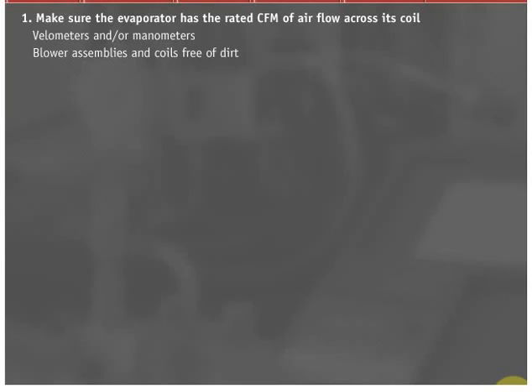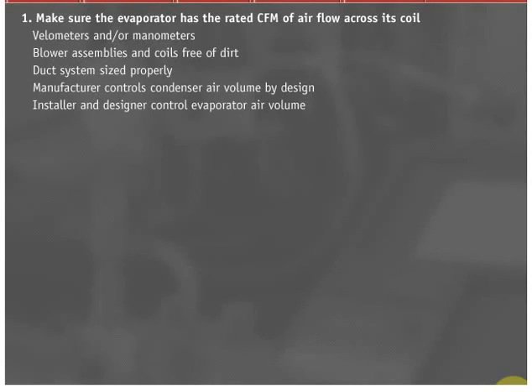Step 1: Make sure the evaporator has the rated CFM of airflow across its coil. Velometers and/or manometers with proper equations will assist in calculating system CFM. Check to see if blower assemblies and coils are free of dirt and that the duct system is sized properly. Remember, the unit manufacturer controls condenser air volume by design, and the installer and designer control evaporator air volume.